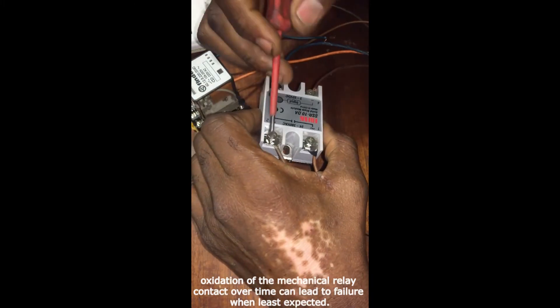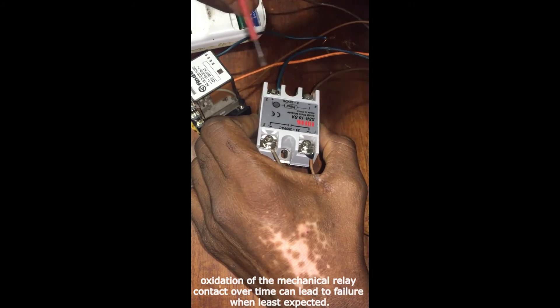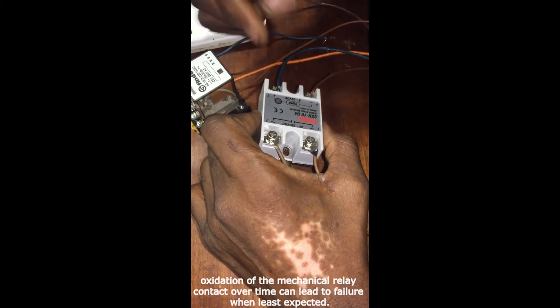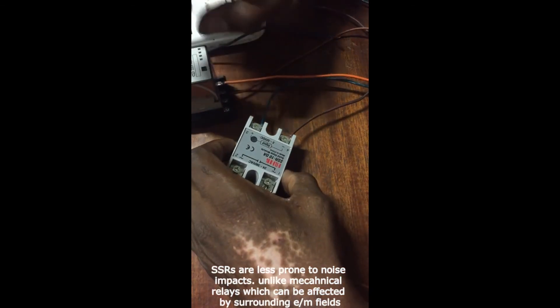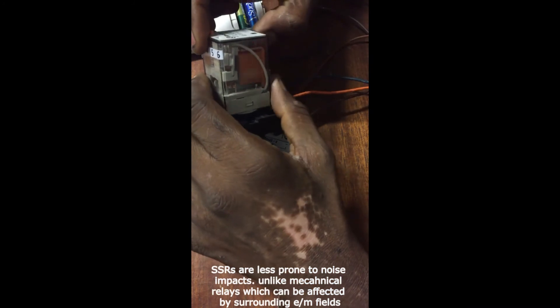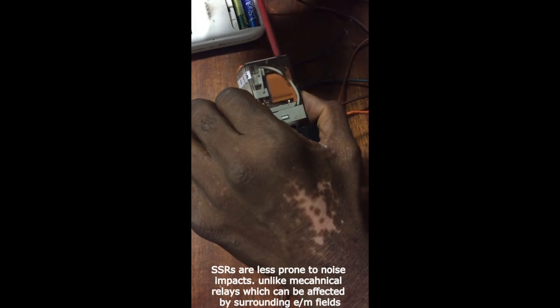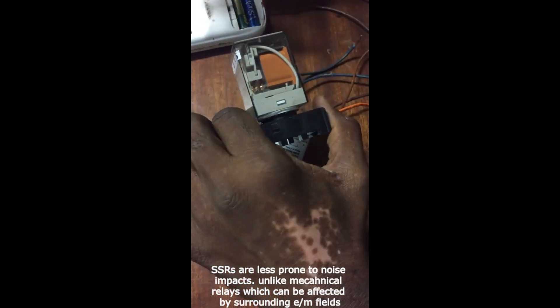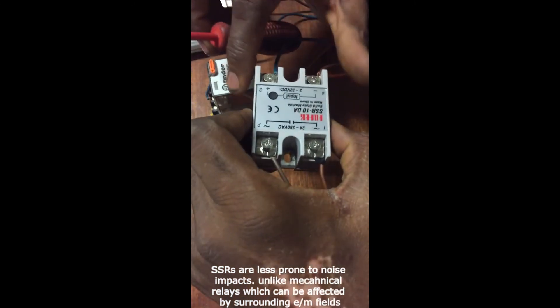Unlike the electromechanical relay, the SSR does not have any moving parts. It could work in extreme locations or in the middle of any place — so long as these terminals are protected from exposure to moisture, they will continue to perform. Thirdly, the SSR is not prone to noise impact in terms of humming, because this electromechanical relay, being an electromagnetic device, has the potential to be impacted by electromagnetic fields surrounding it. So it cannot be used in a place where there is possibility of an EM field existing. In that situation, you have to use an SSR.